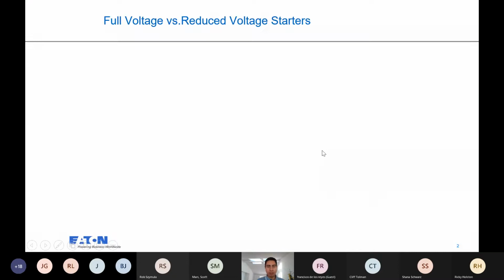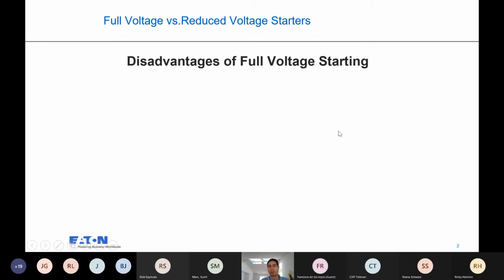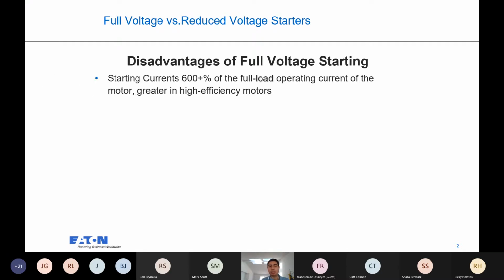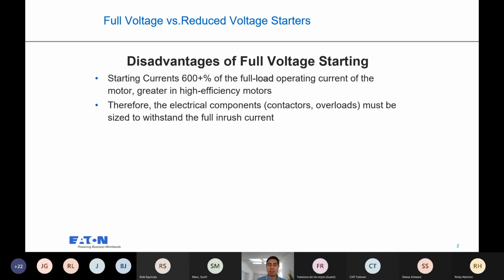All right. So let's begin with energy savings. That's why I was initially brought on here. We want to talk about full voltage, reduced voltage starters, across the line, and variable speed. So what are the disadvantages of full voltage starting? I do have a graph to show this. You have an inrush going into your motor, and it's about 600% of the full load operating rating. This creates mechanical stresses, electrical stresses, and let me see.